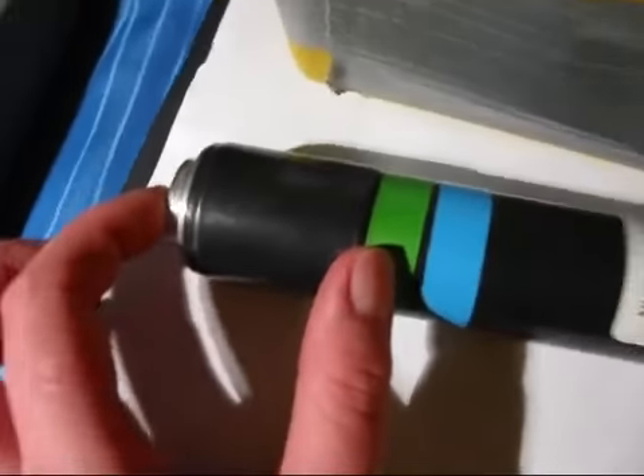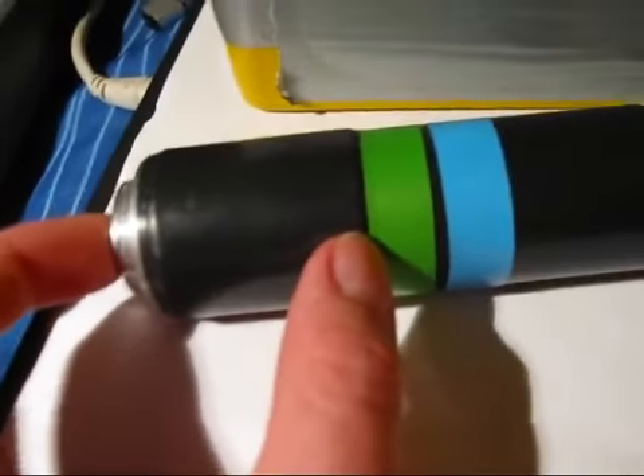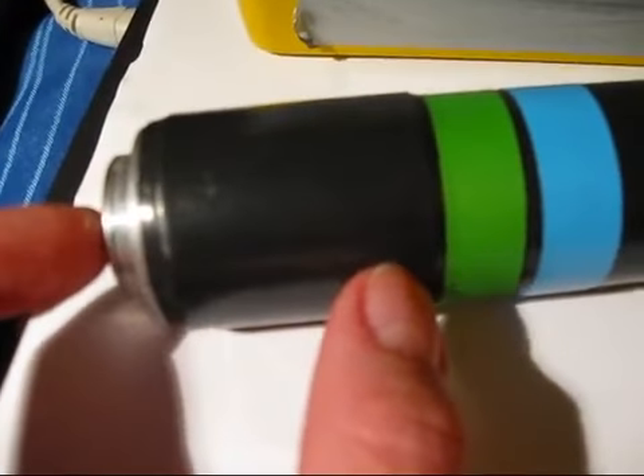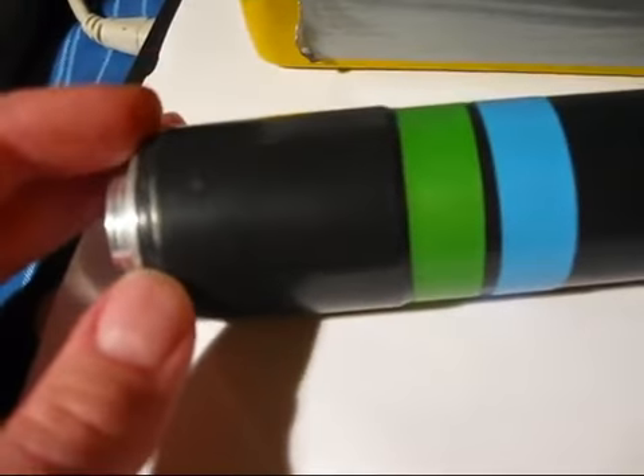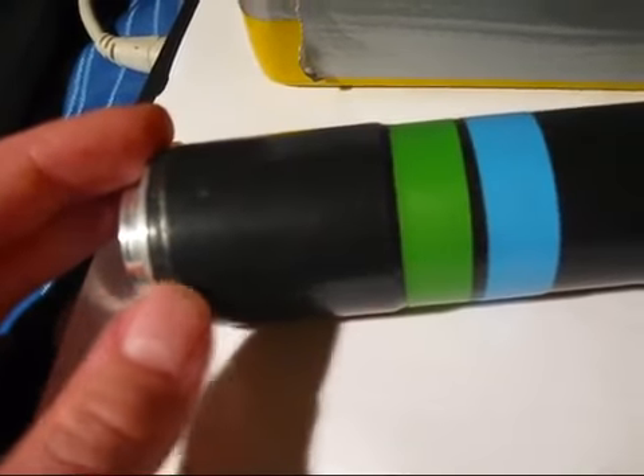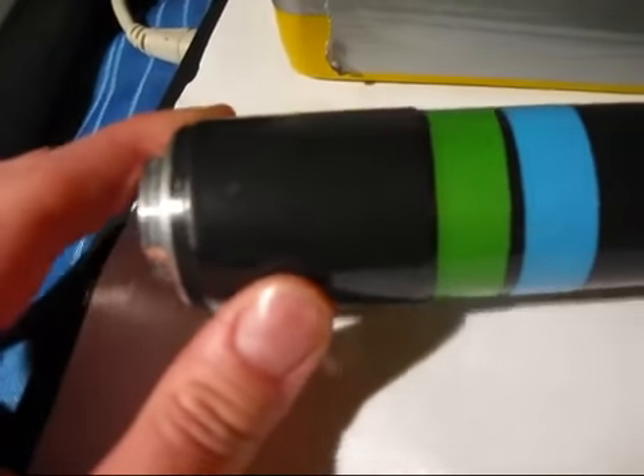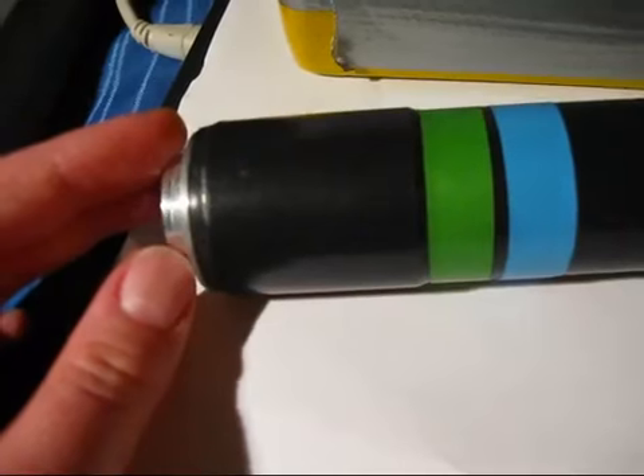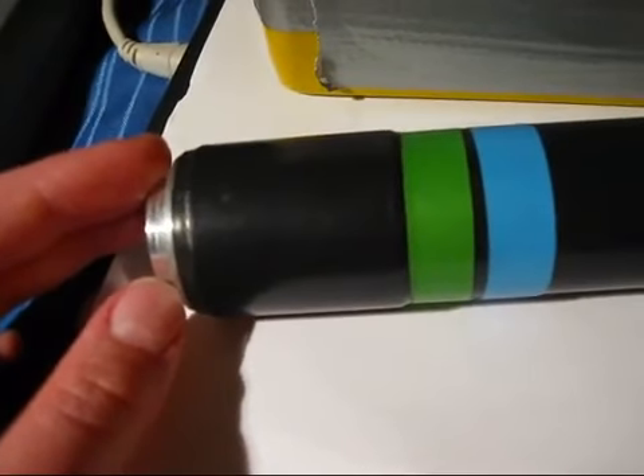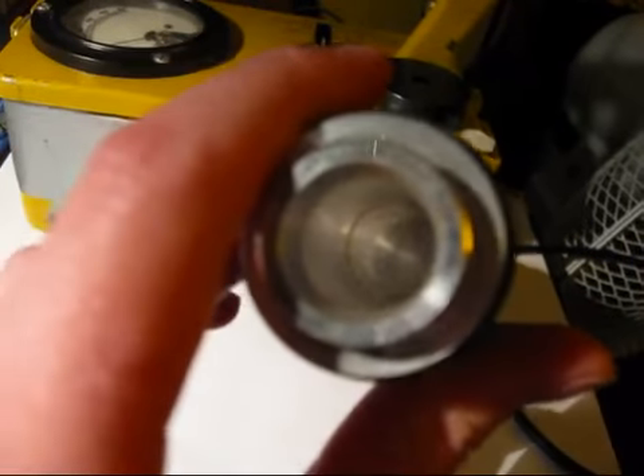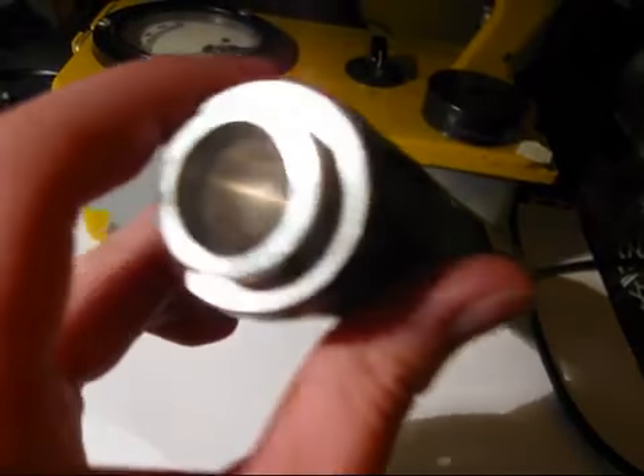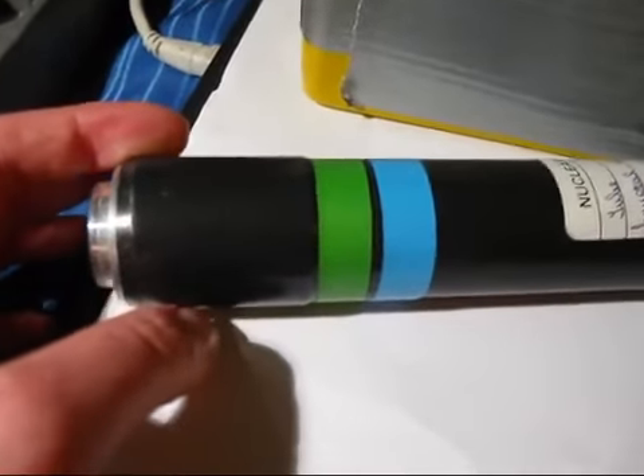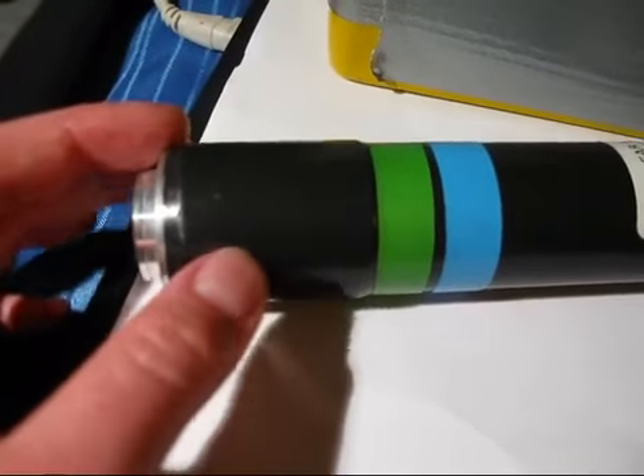So the top of this device is obviously a sodium iodide crystal that is doped with thallium, and in this crystal little scintillations will appear, thus the name, scintillation counter. Scintillations are basically little flashes of light that are caused within this crystal by ionizing radiation. As you can see, the head of this probe has a hollow end, so you can insert a probe into it, and it is surrounded by the crystal. But you cannot see this crystal, obviously.